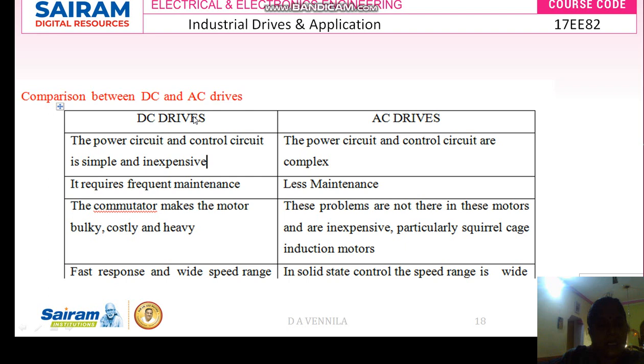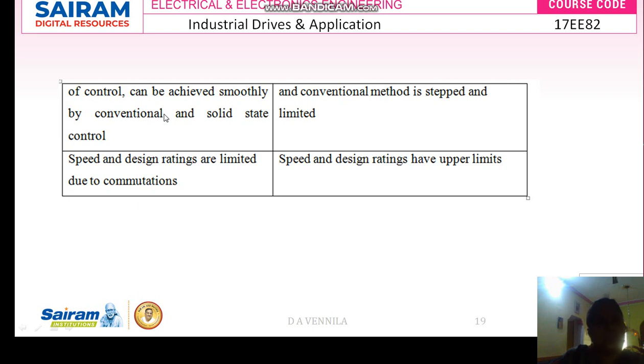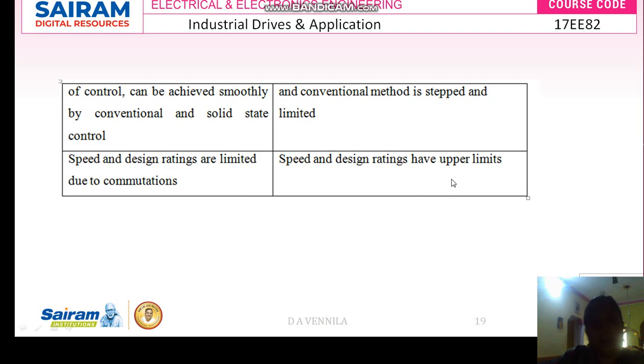In DC drives, there is fast response and a wide speed range. But in AC drives with solid state control, the speed range is wide but fast response is limited. The speed and design ratings are limited in DC drives due to commutation. This is very important — because of commutation in DC drives, the speed and design ratings are limited. But in the case of AC drives, the speed and design ratings have a very high upper limit.